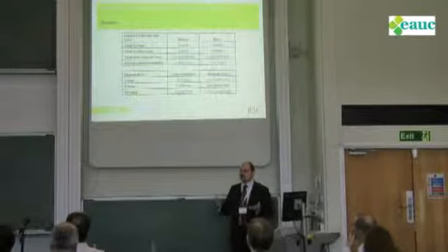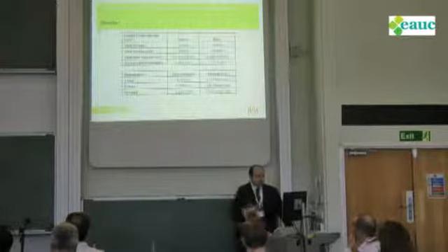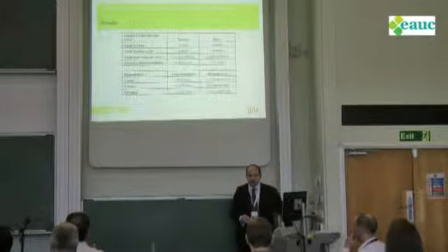It's all very well we can talk about all these best practices, but what do they mean in real life? Well, this is our case study. We basically had an IT load of 120 kilowatts and a facility load of 264 kilowatts. So we were pretty inefficient. That works out at about 2.2, 2.3 PUE.